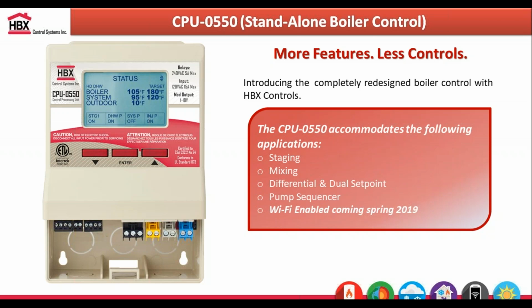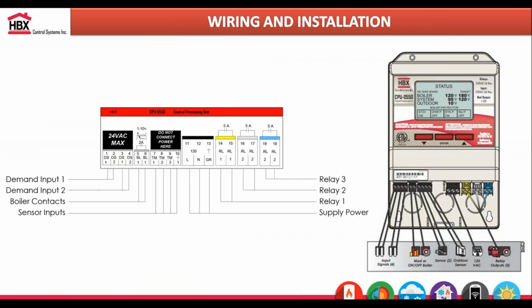When you power up the CPU 550, you can use it as a staging controller for your boilers, or you can use it as a staging controller and control a mixing device. There are 2 different options of 2 different set points you can control with the 550, or you can just use it as a pump sequencer controller as well. So you get 5 different application modes built into one controller, which is real nice.